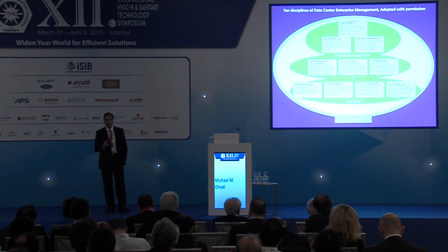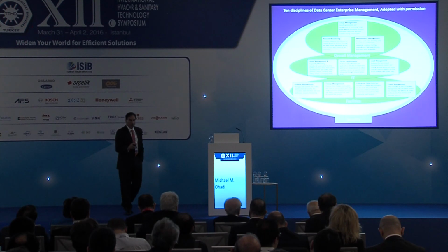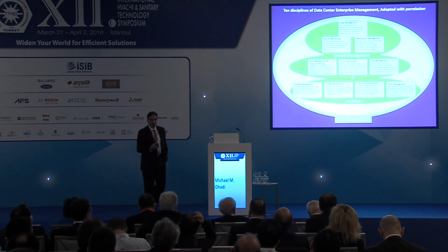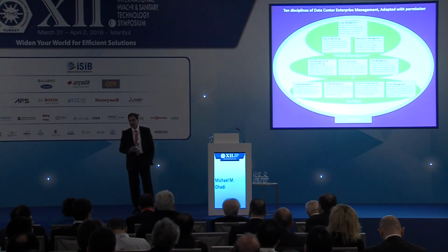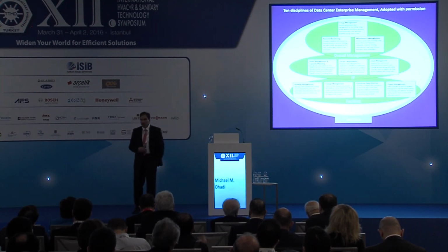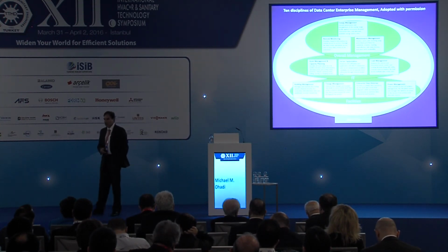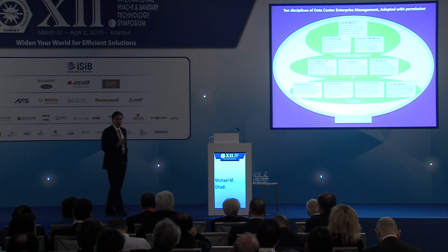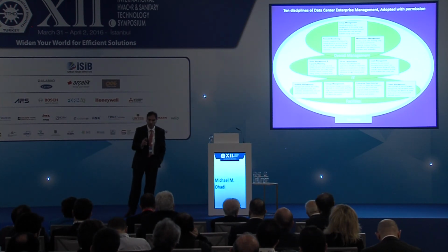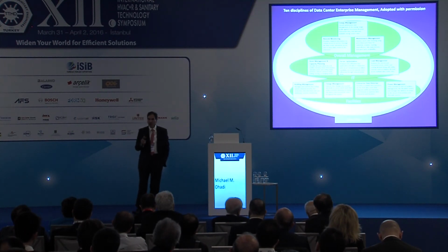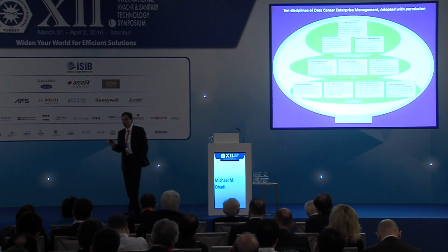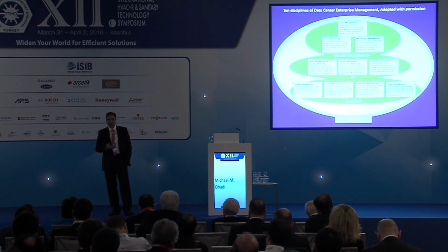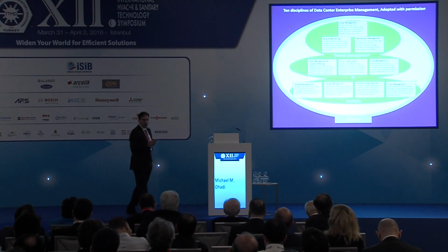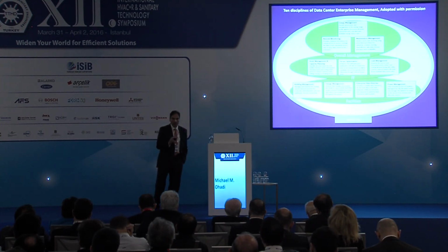Anything and everything you do, you have to go by standards. Even within standards, you have to stay conservative, because this is a mission-critical facility - not a typical building where cooling system failure for a day just means people sweat a little and it's done. The computer modeling software will project catastrophe failure for you - you could put in the software, what would happen if I lose all of the power? The models are improving, but the software will show that most data centers can only survive about a couple of minutes, meaning just enough...